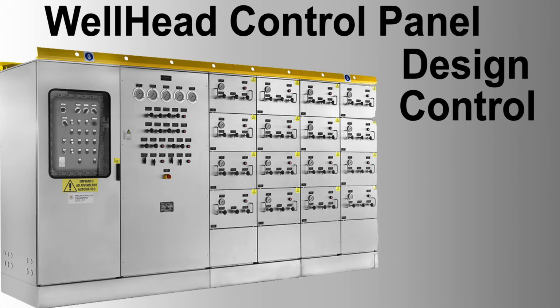Temperature control loop. Sensor: temperature sensor, range 50 degrees Celsius to 150 degrees Celsius, accuracy 0.5 degrees Celsius. Actuator: heater cooler, 4 to 20 milliamps control signal. PLC RTU: PID control algorithm, set point adjustment via HMI SCADA. Feedback: real-time temperature data to PLC RTU. Alarm: high-low temperature alarms. Shutdown: ESD if temperature exceeds critical limits.